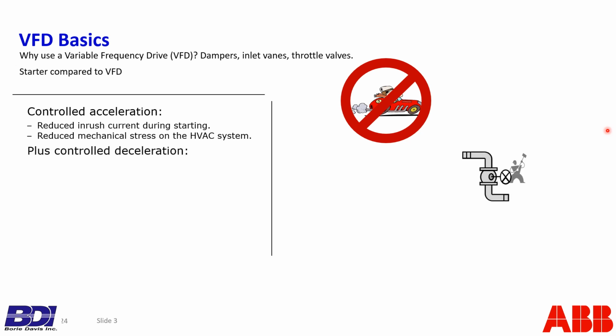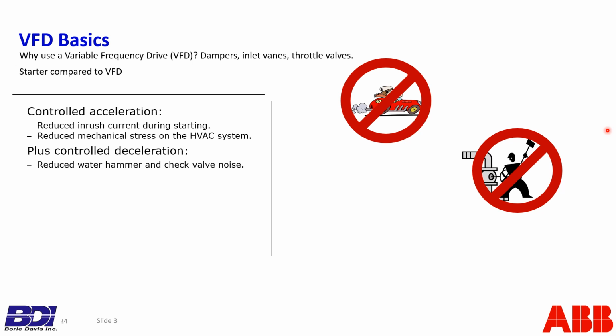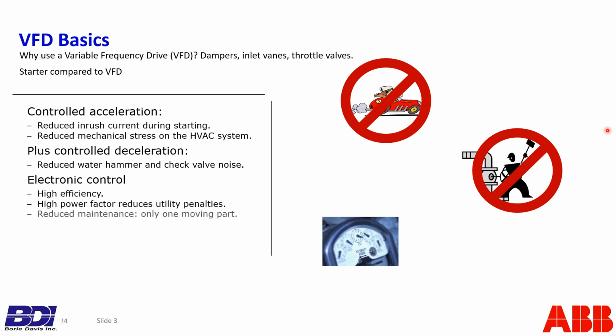Okay. Additionally, on deceleration, on stopping, a starter's just going to let go of the motor and it's going to coast to a rest. Well, if that's a pump that you're driving, you're going to feel and potentially you're going to hear check valve slamming, and that causes things to vibrate, and that also causes things to wear out. Okay, so with the drive, you can command the stop function to actually ramp the motor down from speed and let go of it once it gets down to 0 voltage, 0 frequency.